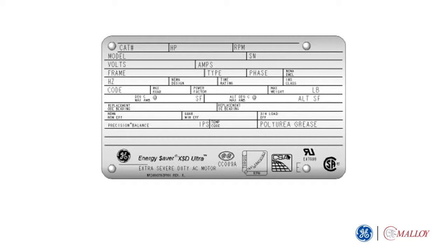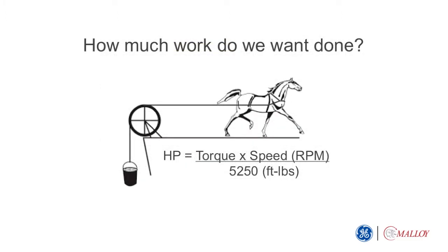The number one definition is power, measured in either horsepower for NEMA standardized machines or kilowatts, typically for IEC standardized machines. Horsepower measures the amount of power a motor can give, defined by torque times speed, divided by 5,250 feet-pounds.